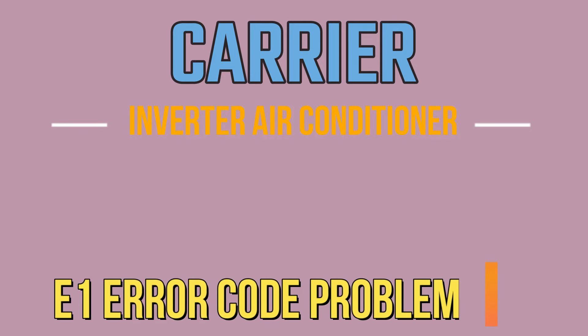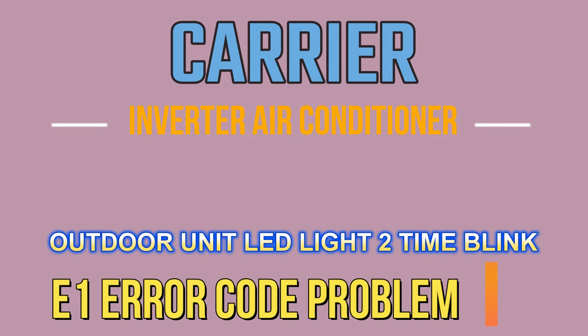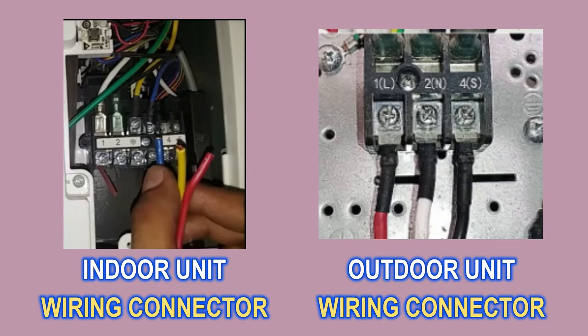In today's video, I am going to tell you that if you have a Carrier inverter AC and an E1 error is coming in that AC, and the LED light of the outdoor unit is blinking two times, then how can you fix this error. This error is an indoor unit and outdoor unit communication error, and it can occur due to four reasons.